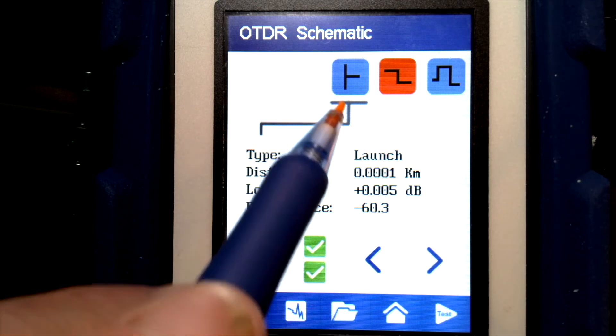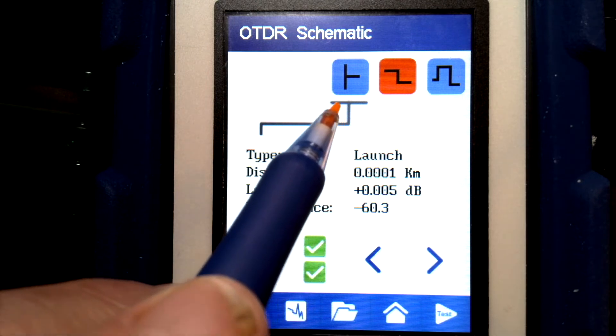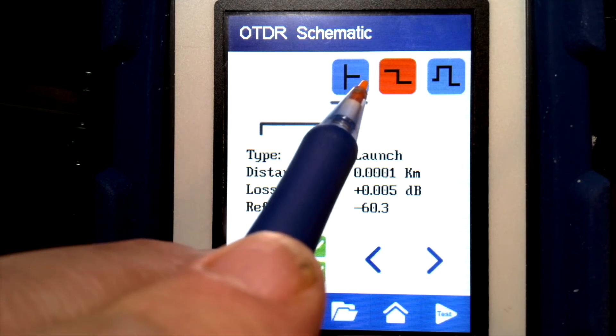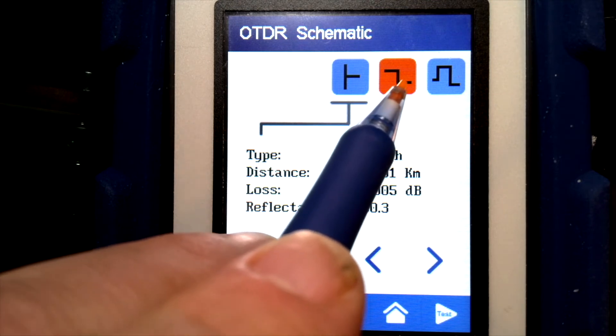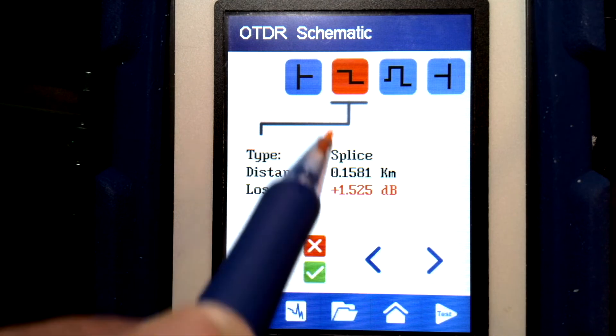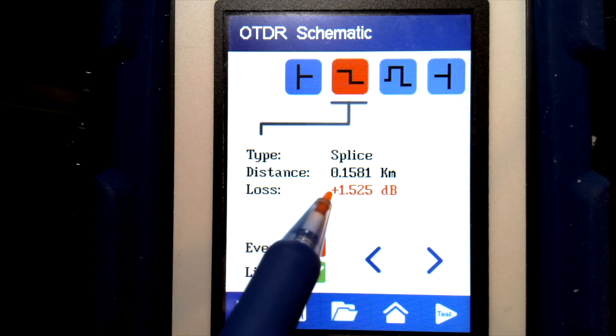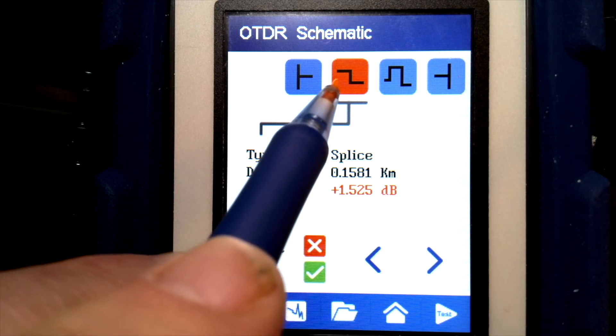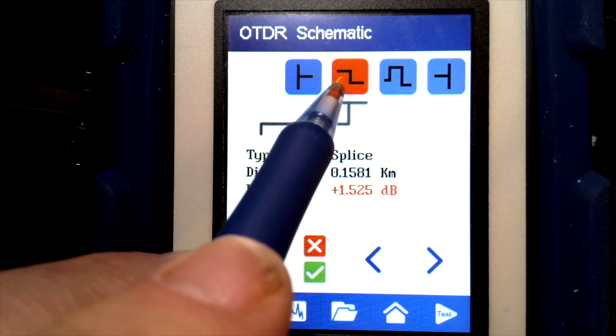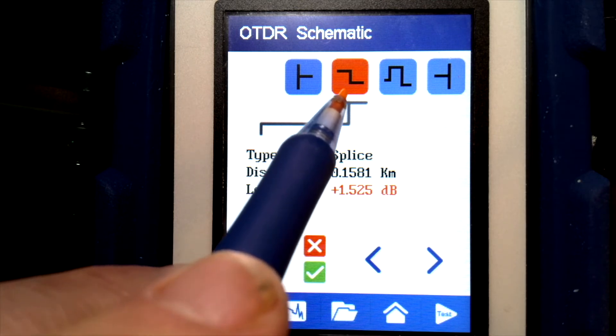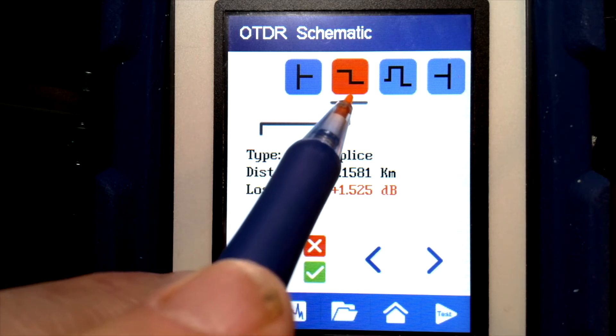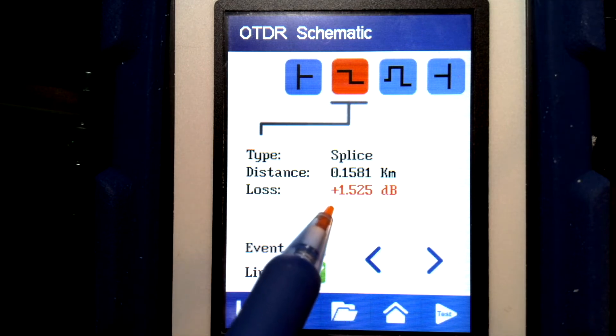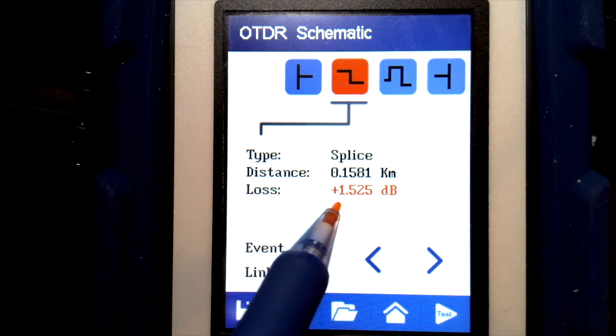Right now it's showing us a schematic view where we have symbology indicating the events of the fiber. We can touch on one of those and it will show us what type of event it is, where it is, and how much loss it has. This particular splice is shown in red because it exceeds the loss budget for the limit we have selected — it's a loss of 1.5 dB.